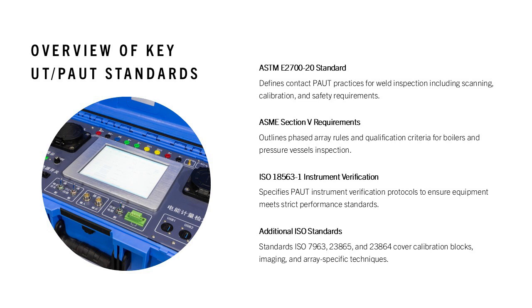ISO 18563-1:2022 provides detailed specifications for PAUT instrument verification to ensure equipment meets performance thresholds. Additional standards such as ISO 7963, ISO 23865, and ISO 23864 address calibration blocks, advanced imaging, and array-specific techniques, ensuring global harmonization of UT and PAUT processes. Together, these standards form a comprehensive framework that guides practitioners in achieving reliable non-destructive evaluations using phased array techniques.